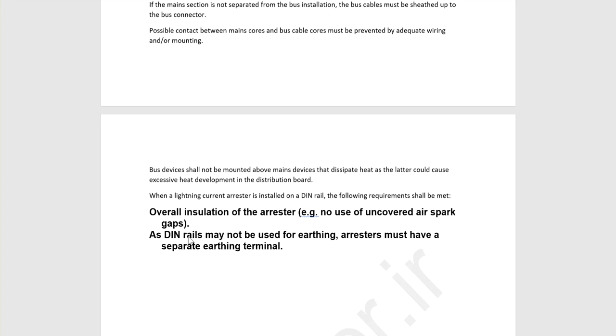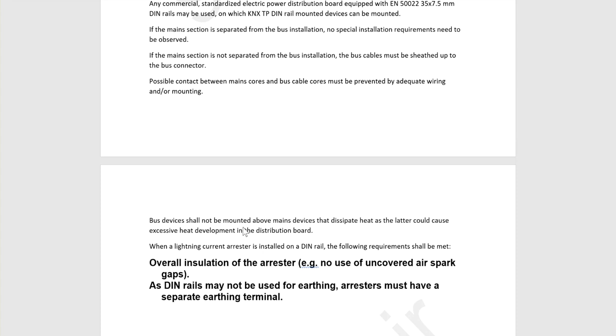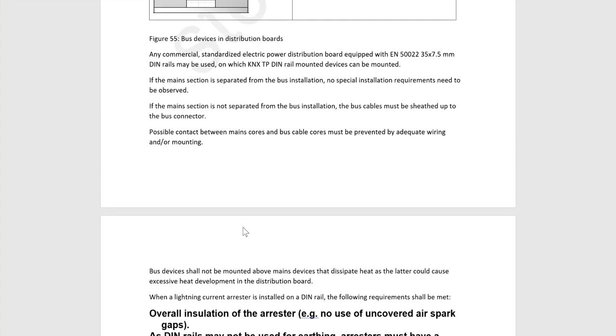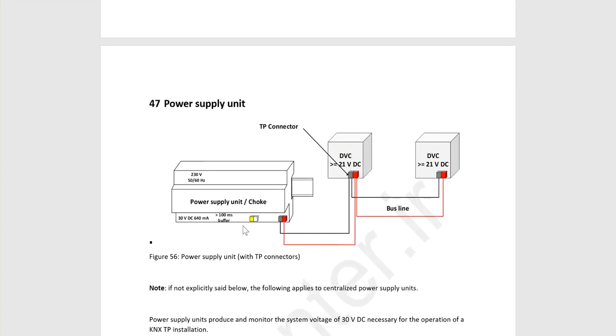Another important thing is a DIN rail may not be used for earthing. Arresters must have a separate earthing terminal. If you use the arrester in your electrical cabinet with KNX devices, you should consider some concerns, as I said. And that's it. I think it is enough for now.